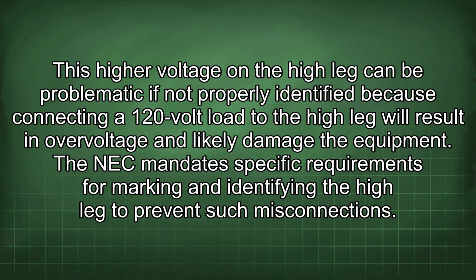This higher voltage on the high leg can be problematic if not properly identified, because connecting a 120 volt load to the high leg will result in overvoltage and likely damage the equipment. The NEC mandates specific requirements for marking and identifying the high leg to prevent such misconnections.